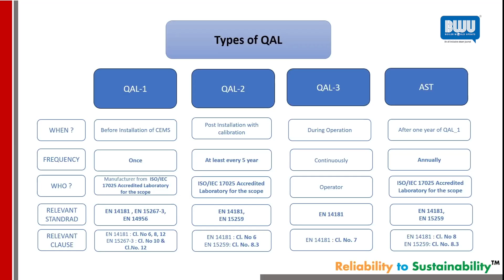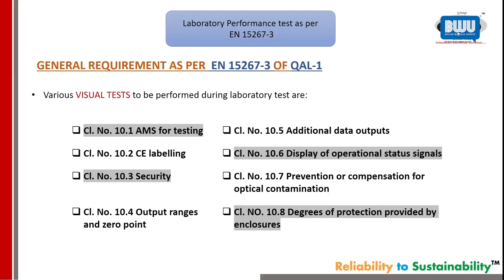So this was a general requirement. So this will be called a visual test, as I explained before, you go for QAL 1, that is 15267-3. These are the primary requirements of the CE labeling. You must have 61010 tested equipment for EMC, security, output range, then display of operational status. So it comes with a diagnostic feature also. So if my system is installed and anything goes wrong, the pressure or flow, it should pop up on my screen. It's not only a measuring equipment. It should ensure that my system works properly and keeps giving me information continuously about what is happening.